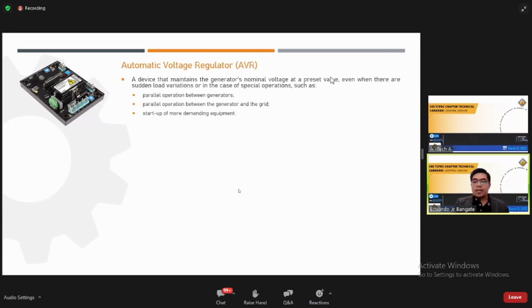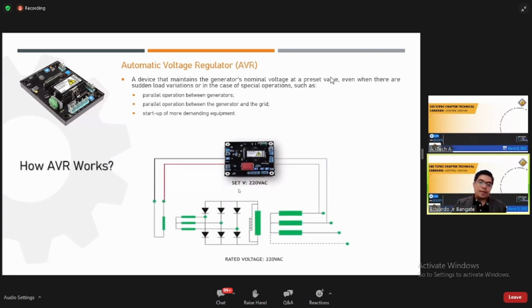Every generator requires certain voltage and currents for its excitation. Therefore, the AVR must be provided according to specific generator requirements. Now, let's see how AVR works and how it controls the output of the generator. I have here a simple circuit. This is a shunt excitation method, and we have here an example of an AVR. Rated voltage is, for example, 220 volt AC. So set voltage is 220 volt AC.